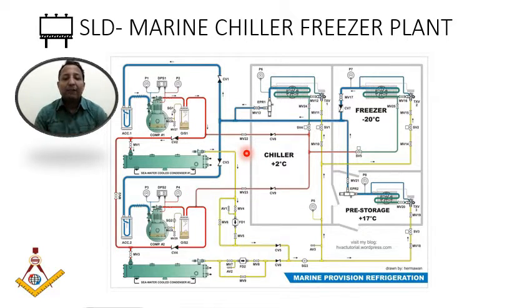Let's take an example of the pre-storage room. When a frozen container from the shore comes inside, it doesn't need to go directly into the chiller freezer room. So some material is kept in the pre-storage room at plus 17 degrees Celsius. The freezer room is required to be kept at minus 20 to minus 24 degrees Celsius, and the chiller room is kept at plus 2 degrees Celsius.